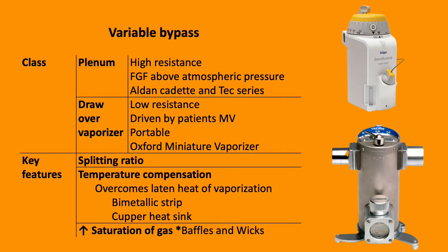Variable bypass — plenum vaporizers — are high resistance. Fresh gas flow is above atmospheric pressure, as shown in the top right corner with a sevoflurane vaporizer. Examples include the Tec series.